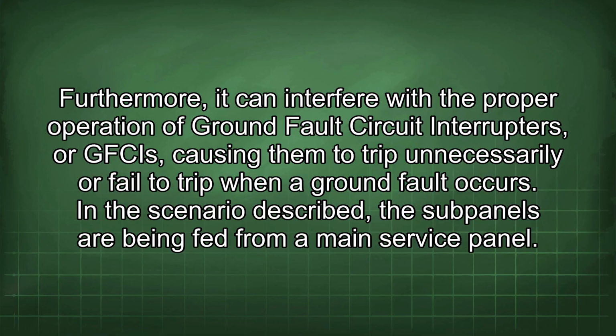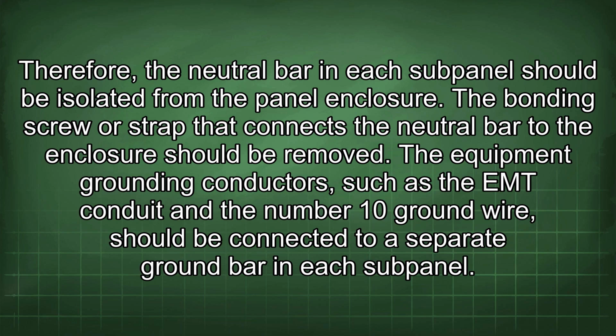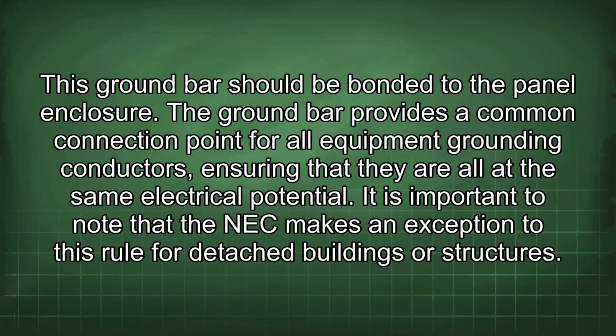In the scenario described, the subpanels are being fed from a main service panel. Therefore, the neutral bar in each subpanel should be isolated from the panel enclosure. The bonding screw or strap that connects the neutral bar to the enclosure should be removed. The equipment grounding conductors such as the EMT conduit and the number 10 ground wire should be connected to a separate ground bar in each subpanel. This ground bar should be bonded to the panel enclosure. The ground bar provides a common connection point for all equipment grounding conductors, ensuring that they are all at the same electrical potential. It is important to note that the NEC makes an exception to this rule for detached buildings or structures.